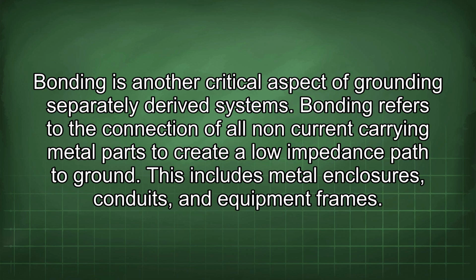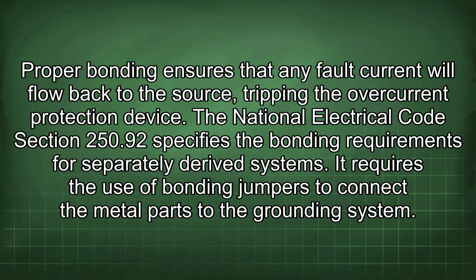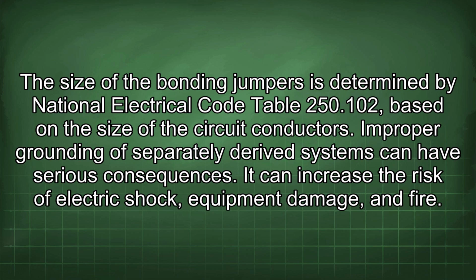Bonding is another critical aspect of grounding separately derived systems. Bonding refers to the connection of all non-current carrying metal parts to create a low impedance path to ground. This includes metal enclosures, conduits, and equipment frames. Proper bonding ensures that any fault current will flow back to the source, tripping the overcurrent protection device. The National Electrical Code Section 250.92 specifies the bonding requirements for separately derived systems. It requires the use of bonding jumpers to connect the metal parts to the grounding system. The size of the bonding jumpers is determined by National Electrical Code Table 250.102, based on the size of the circuit conductors.